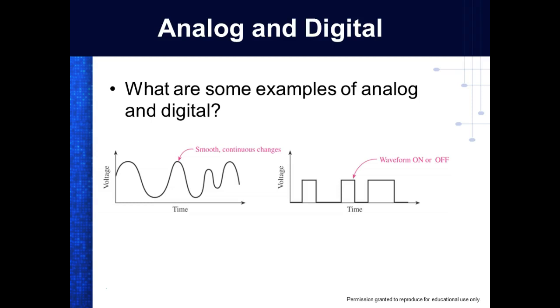On the Siemens, you can actually tell it that you have 0 to 5 volts, but you have to tell the PLC what limits you have. This one is from 0 to 10 volts. Digital is either what? On or off. Now the voltage level on digital depends on what's recognized by the input ports on the PLC. Just about all PLCs, I'm not saying all of them, the predominant number of them use 0 volts for off, and 24 volts for on. And that's pretty standard.